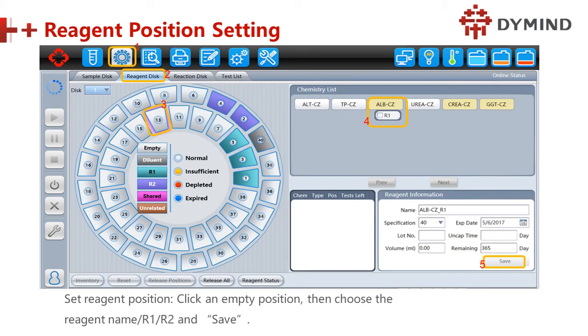After that, we set the reagent position. For the reagent position, we check and click an empty position. This is empty, anyone. We found an empty one from here. This is the setting: reagent setting, reagent disk, and set the position. Click here, and choose the name R1 and R2. We set number 4 as R1. After we set R1, this information also comes from the menu, and then save it.